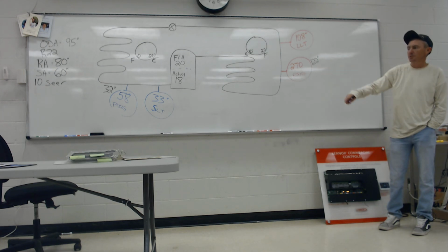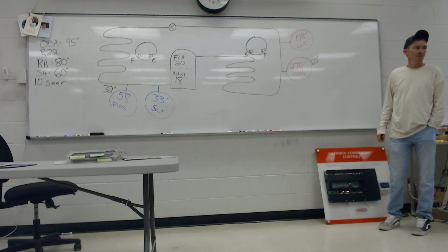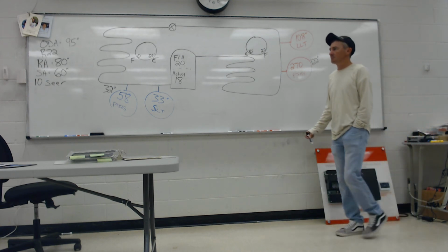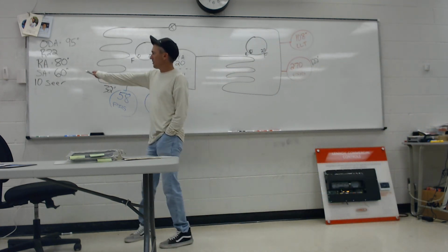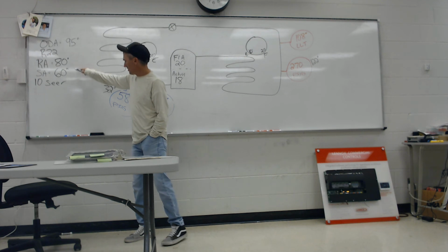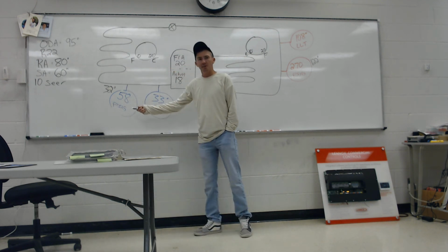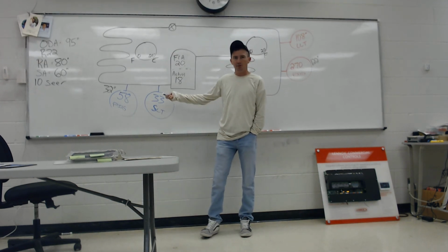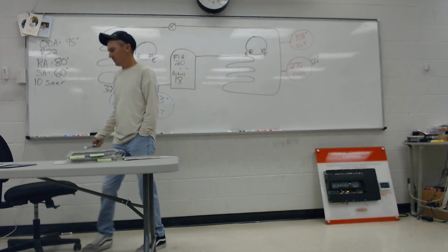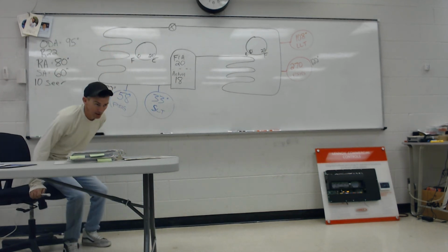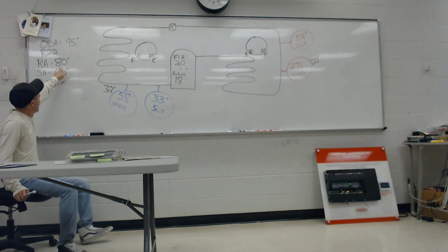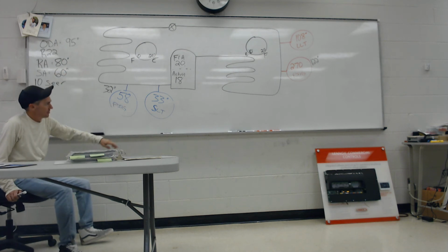That's a red flag: a 32 degree evaporator. She's close to freezing. And if my return air temperature drops a couple of degrees, now I'm definitely below freezing, and it's definitely going to start freezing up if it's not already. You get what I'm saying? The load on the evaporator starts dropping, and then the suction pressure is going to drop.